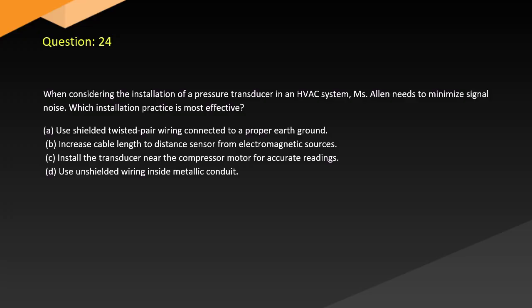Question 24. When considering the installation of a pressure transducer in an HVAC system, Alan needs to minimize signal noise. Which installation practice is most effective? A. Use shielded twisted pair wiring connected to a proper earth ground. B. Increase cable length to distance sensor from electromagnetic sources. C. Install the transducer near the compressor motor for accurate readings. D. Use unshielded wiring inside metallic conduit.